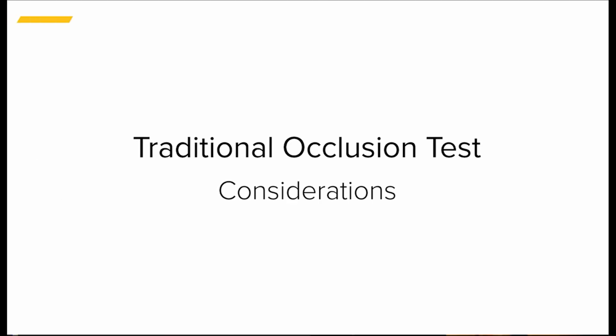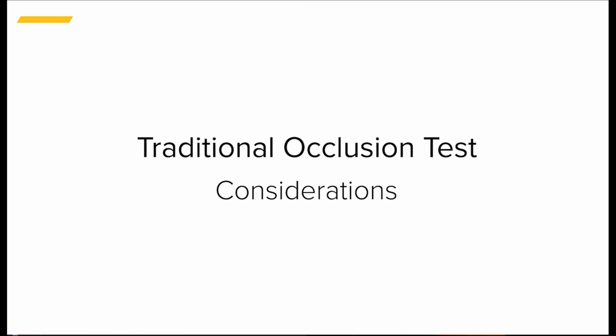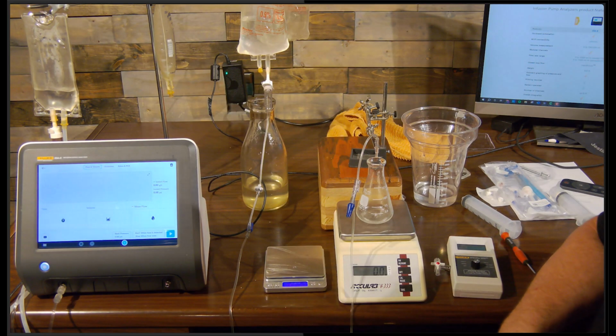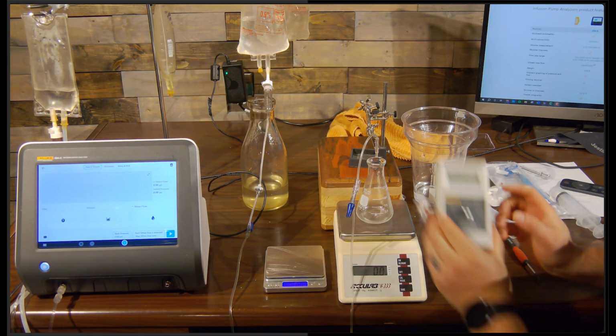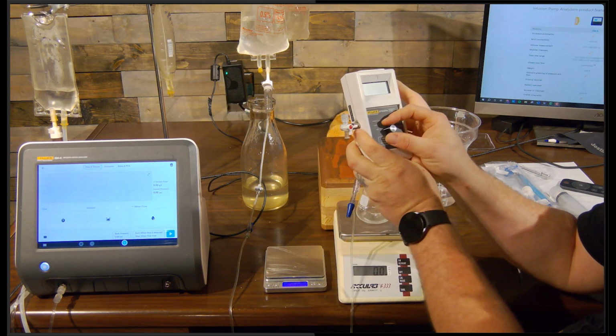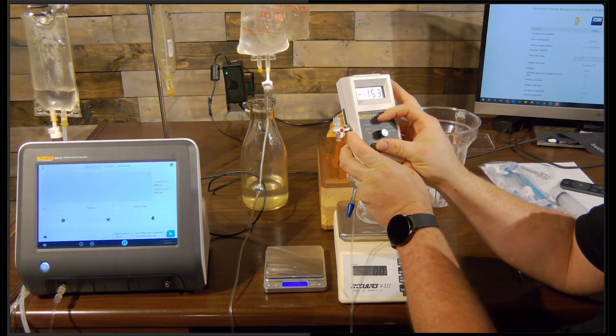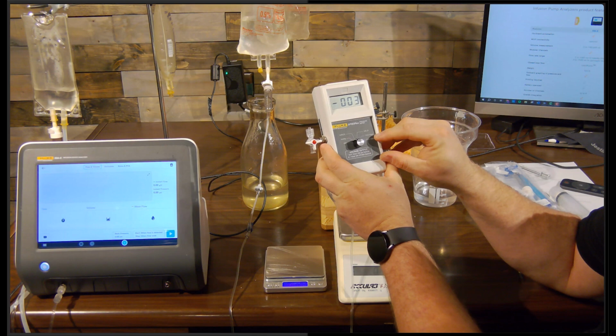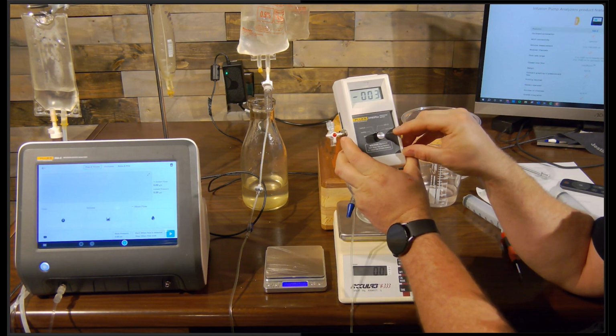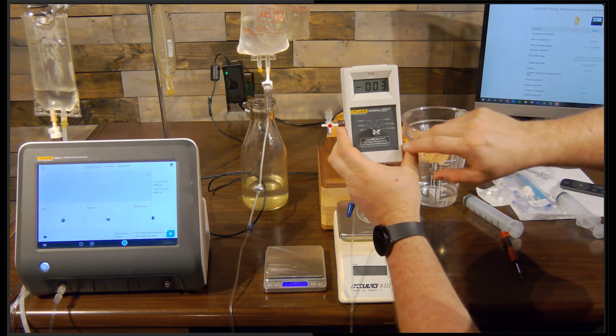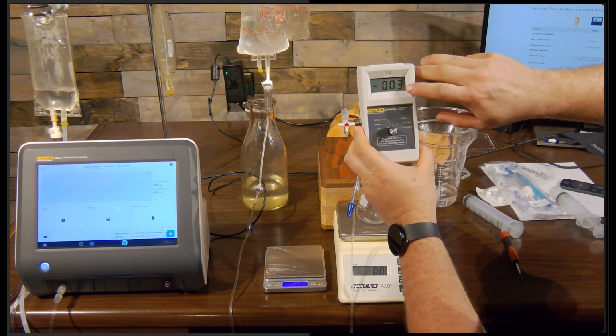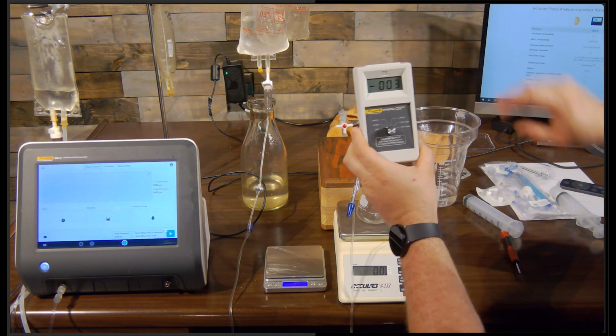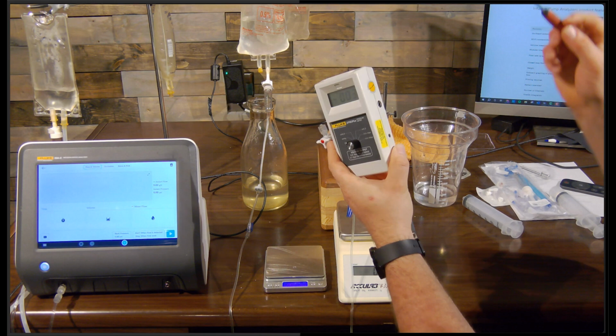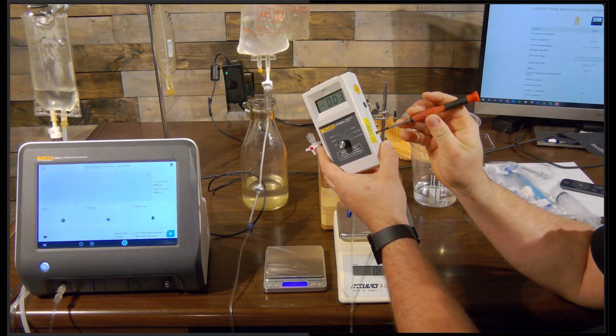And then we'd have to do some occlusion tests. There's an upstream occlusion test where you just pinch a hose, and then a downstream where you need to use a pressure meter. So this is my pressure meter. This is one I used to carry as a field tech, and I would turn it to either millimeters of mercury or PSI, depending on what my service manual calls for. And you're going to notice I just turned it on, and I zeroed this out yesterday, and today I'm reading -3. So the first thing I need to do is zero that back out here.